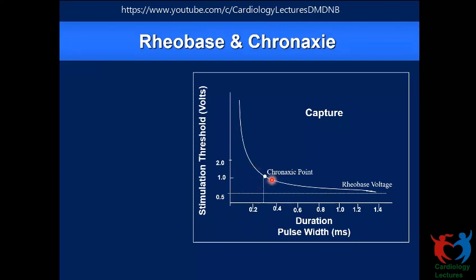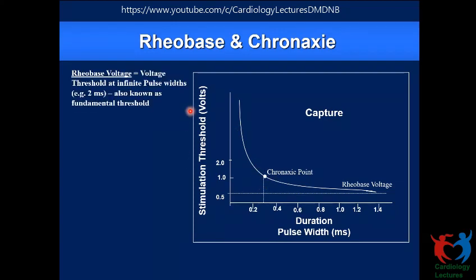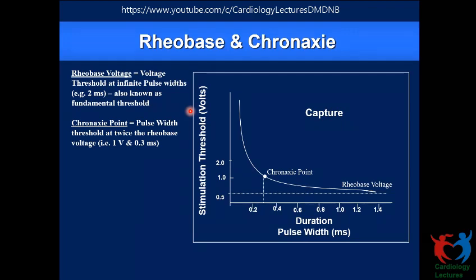But then why is it important at this point, the chronaxie point? That's what we want to examine. So yes, let's assume that we measure the impedance of this pacing circuit, which happened to be 500 ohms. Then at the chronaxie point, it is 1 volt and 0.3 millisecond. We can calculate the energy outgo by applying the formula that we discussed in the previous slide.